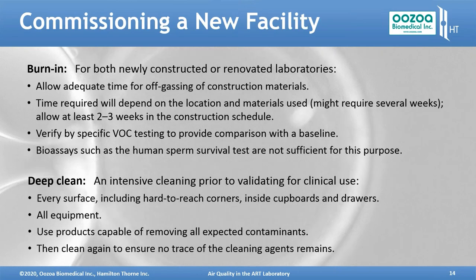If you've built your facility, you're going to commission it, you need a burn-in period. It's not 3 months like people used to say if you've designed it properly and built it properly. But for newly constructed or renovated labs, you need to allow some adequate time for off-gassing of the construction materials. The time this takes will depend on the location of the space and the materials used. It might require several weeks, so you should allow at least 2 to 3 weeks in your construction schedule for this to happen.